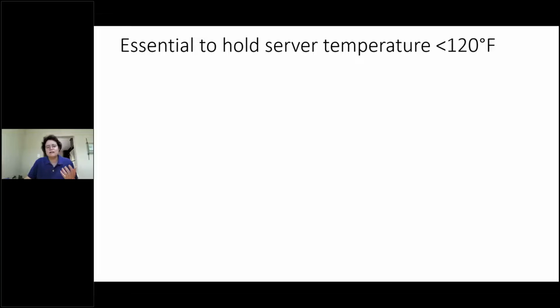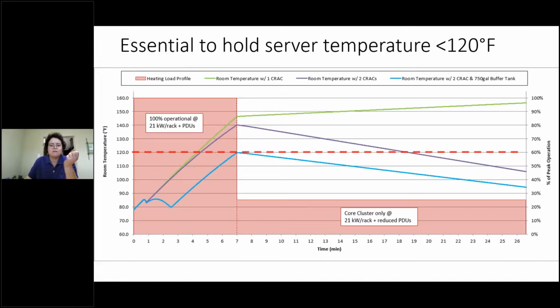This is where the performative aspect comes into play. In the first case, we thought we'll just put in some CRAC units, open up all the doors automatically. But that didn't keep us below 120 degrees, because the air-cooled chiller couldn't get up to speed fast enough, and we didn't have enough thermal mass in the slug in the piping to keep up with it. We said okay, we'll put in another CRAC unit - still not enough.